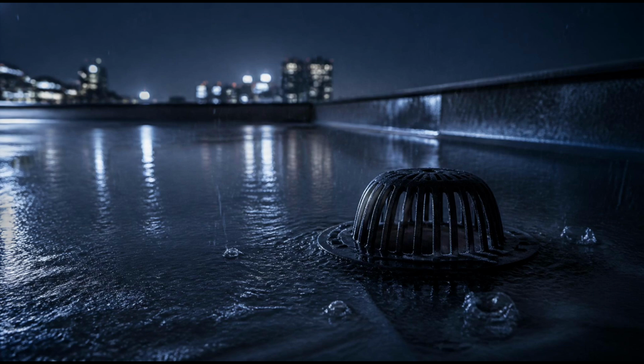In critical installations, basement mechanical rooms for example, where flooding could damage expensive equipment, redundant sump pumps are common. A primary pump handles routine conditions, and a secondary pump sits in reserve, ready to activate if the primary pump fails or if inflow exceeds what one pump can handle alone. In some installations, a battery backup system ensures that the sump pump can continue operating even during a power outage, precisely the kind of event that might accompany the heavy rainstorm causing the flooding in the first place.